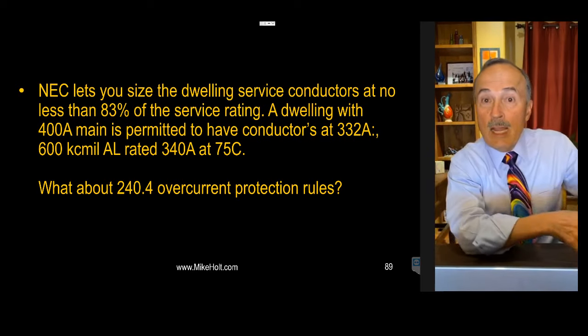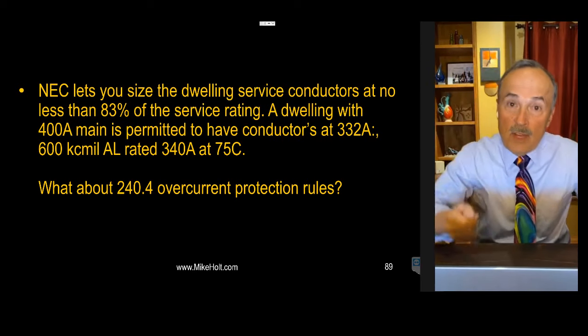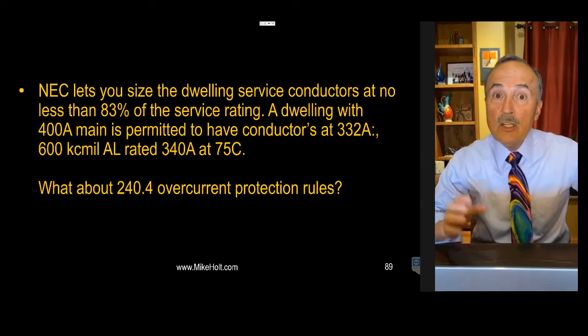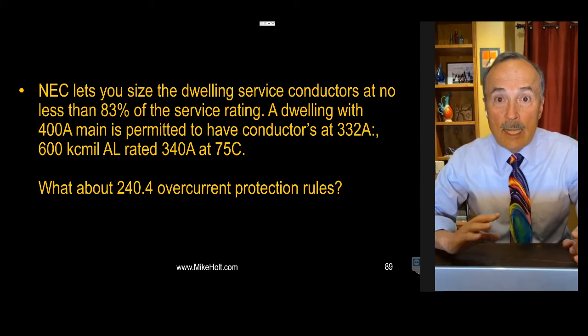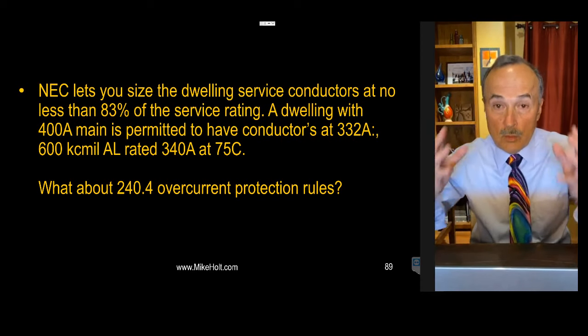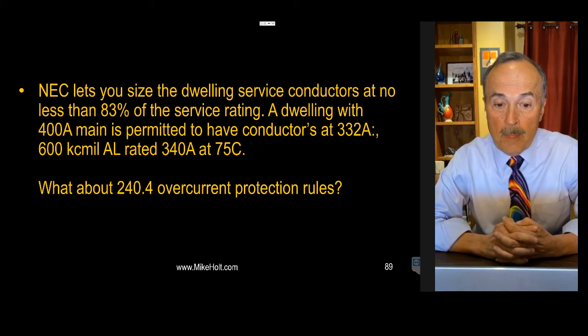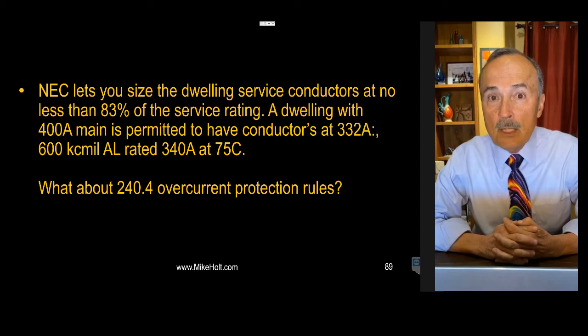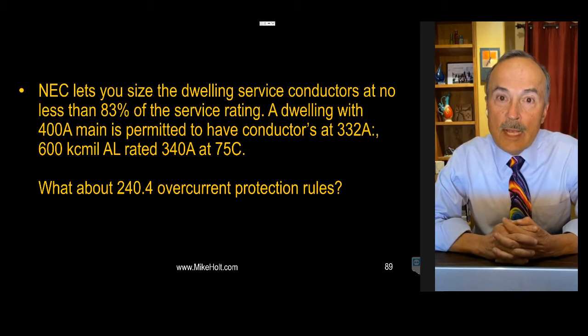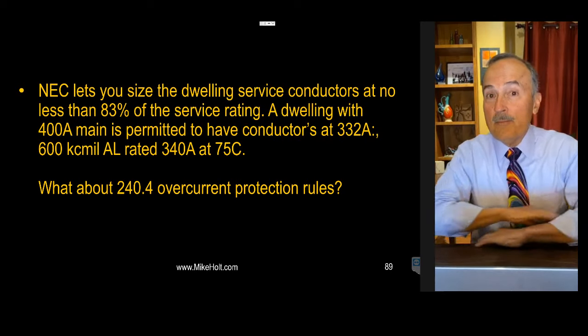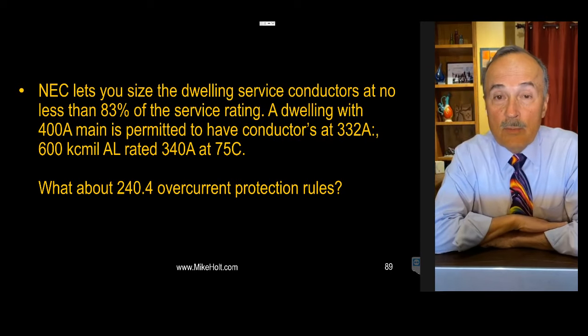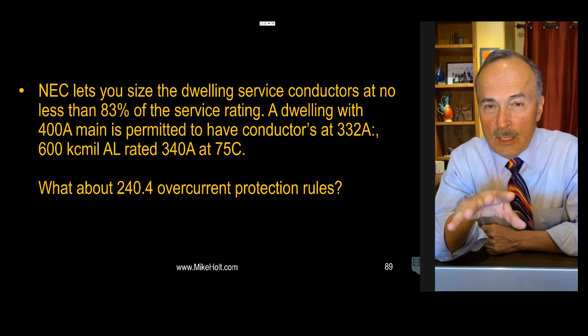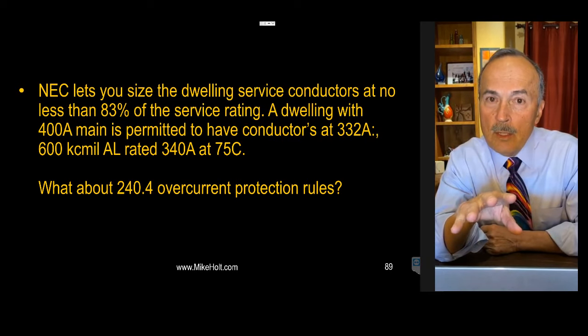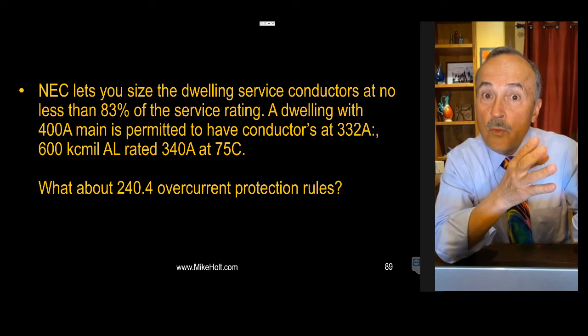A dwelling unit with a 400 amp main is permitted to have a conductor size at 83% of that 400 amps, 332 amperes. If you go to Table 310.16, using the 2020 code as a reference, you go to the aluminum column on the right-hand side, the 75-degree C column, because we are sizing the conductors to terminals. We're not calculating the ampacity of a wire in a raceway or a cable. We're just going to termination, so it has to be 75 C. You can use a 600 kcmil conductor, not kcm, kcmil, and it's rated 340 amperes.